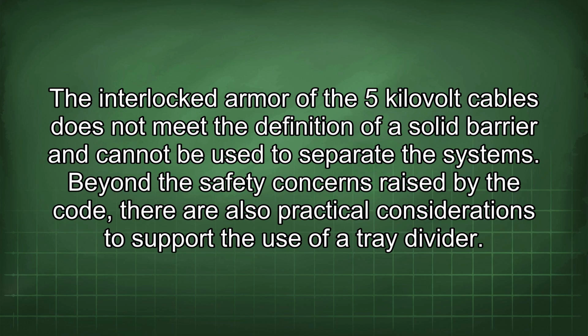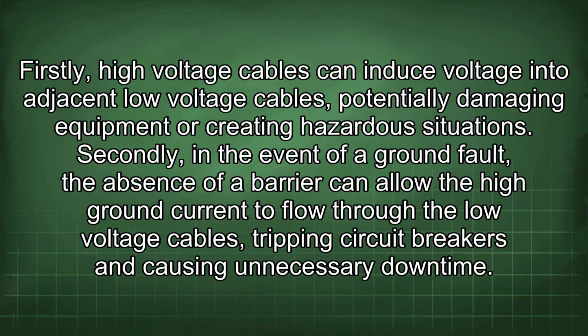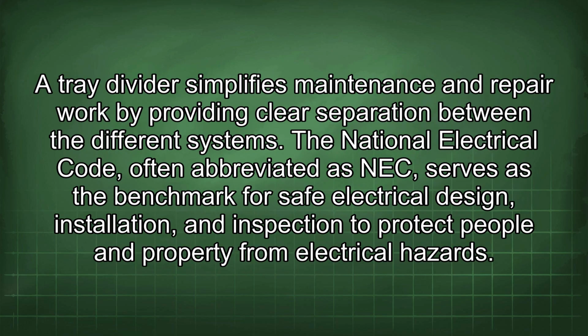Beyond the safety concerns raised by the code, there are also practical considerations to support the use of a tray divider. Firstly, high voltage cables can induce voltage into adjacent low voltage cables, potentially damaging equipment or creating hazardous situations. Secondly, in the event of a ground fault, the absence of a barrier can allow the high ground current to flow through the low voltage cables, tripping circuit breakers and causing unnecessary downtime. A tray divider simplifies maintenance and repair work by providing clear separation between the different systems.